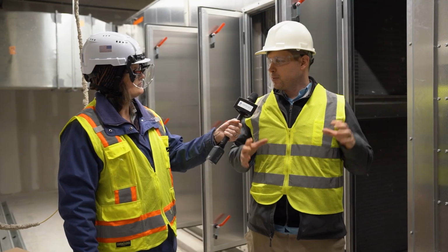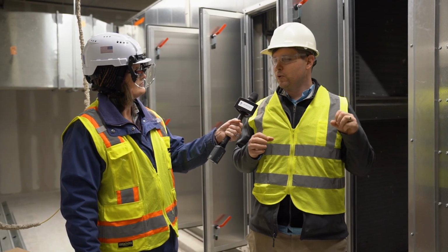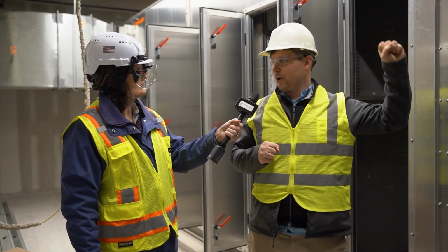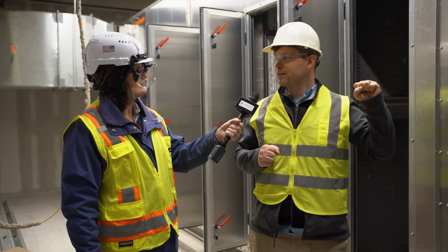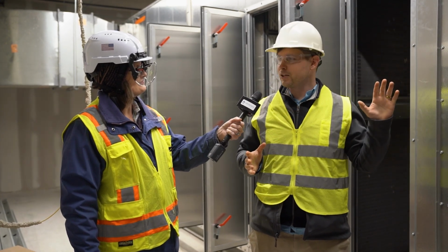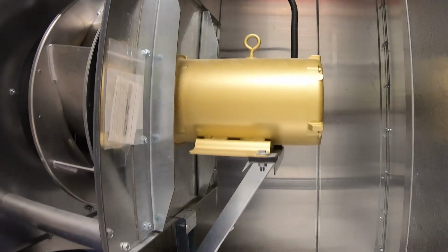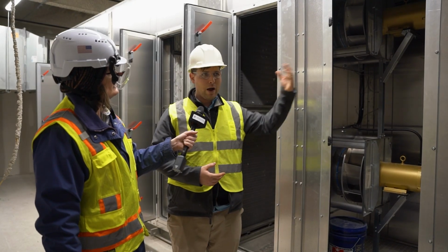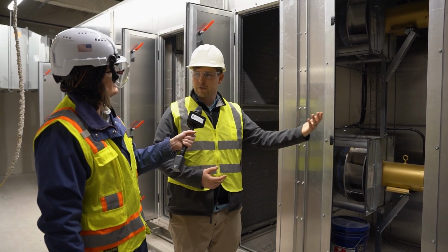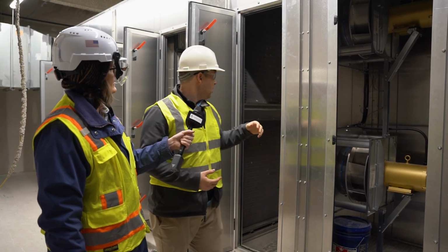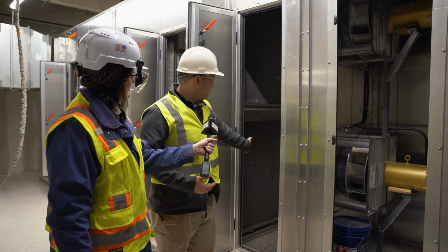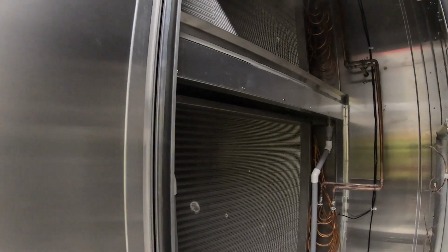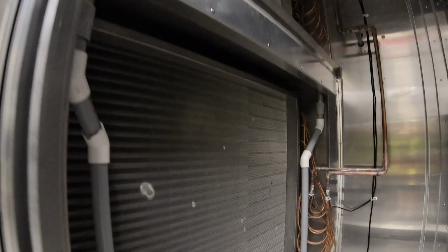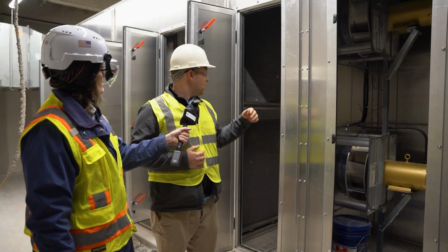A CFM is about the size of a beach ball, so picture this unit spitting out 10,000 beach balls per minute for the entire school day. These are the fans pushing air through the unit, either out into the building or recovering energy and pushing it out of the building. Then we have the coils—since this unit is refrigerant based, these coils do both heating and cooling with refrigerant.